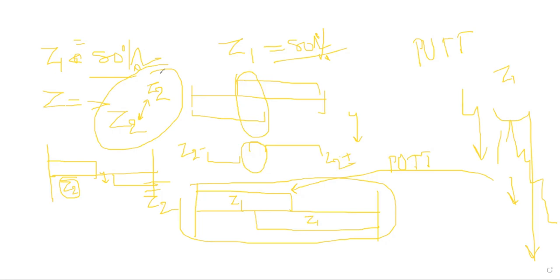Due to the arc of ground fault resistance, there is a very high resistance. That is, you are saying a high resistivity fault? Yes, a very, very rare case. Now, when the high resistivity fault does not come under the impedance level, it goes behind the impedance level. That means automatically it will not come into the picture. The distance relay will not operate in this case.